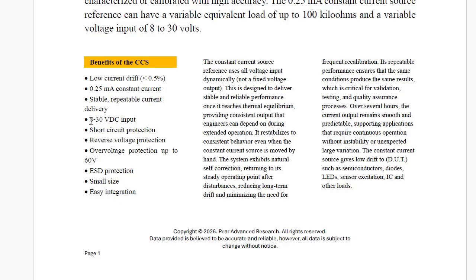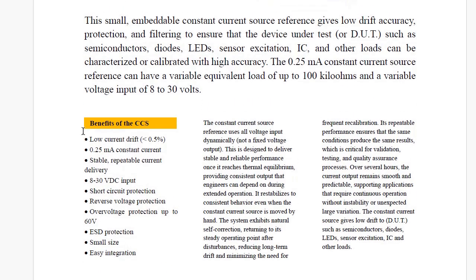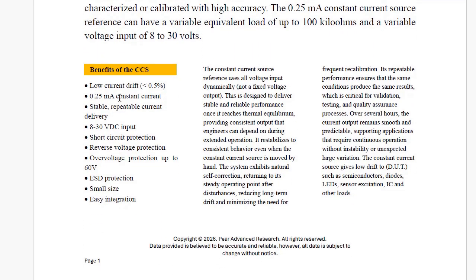With a low load, up to 1,000 ohms, you can go down to 2 volts DC and still achieve 0.25 milliamps. That's an incredibly low power draw, less than 500 microwatts at 2 volts with a 1,000 ohm equivalent load.